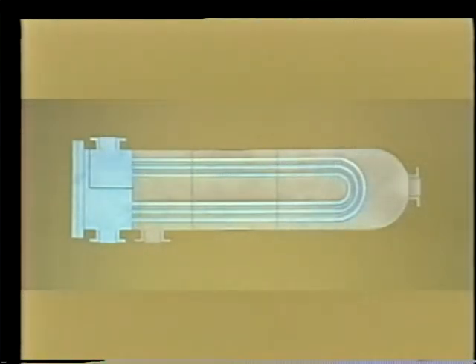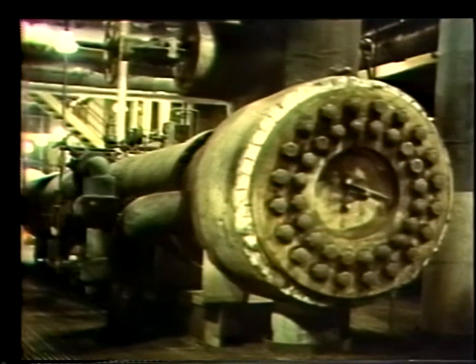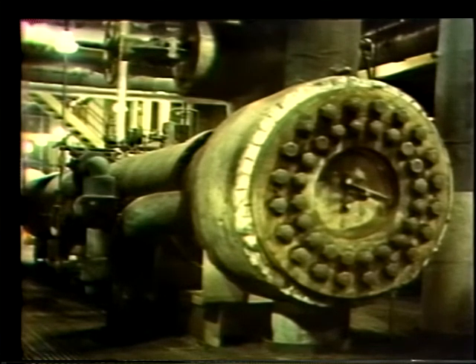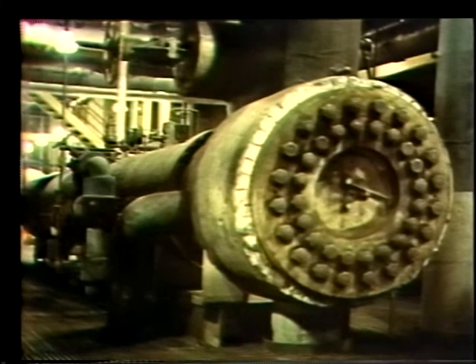If we want a simplified picture of this heater: instead of water going through straight tubes in two passes, we've got steam flowing through U-tubes and being condensed as it heats the oil. Instead of lube oil, we're pumping fuel oil through the shell side. Just like the fuel oil is preheated before it's sent to the boiler, feed water going into the boiler is preheated to make it easier to turn into steam. This feed water heater uses steam to heat the incoming feed water. What's different about this heater is that the steam goes through the shell and condenses on the outside of the tubes. The feed water comes into the lower half of the header and passes through the U-tube bundles to be pumped out on its way to the boiler.